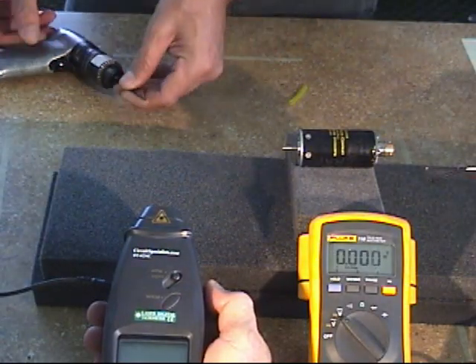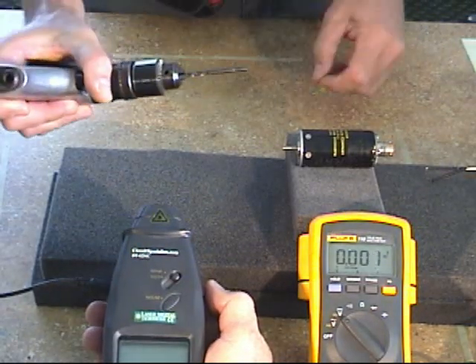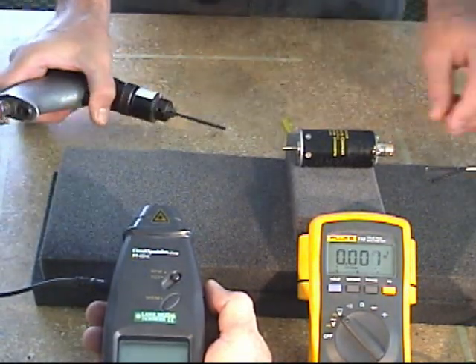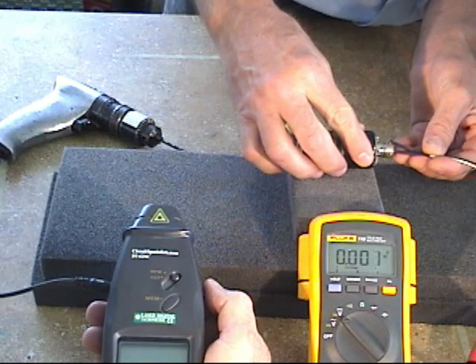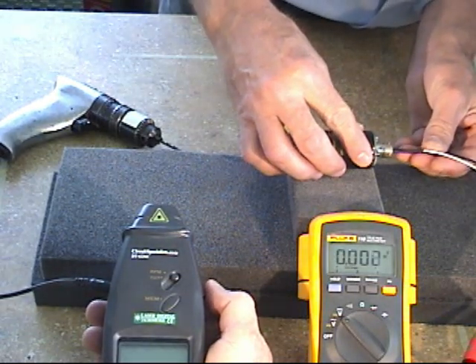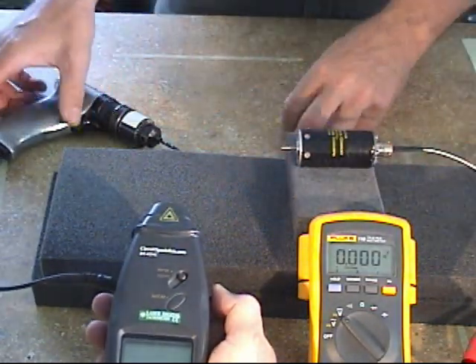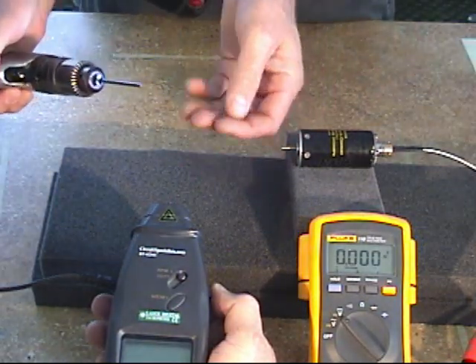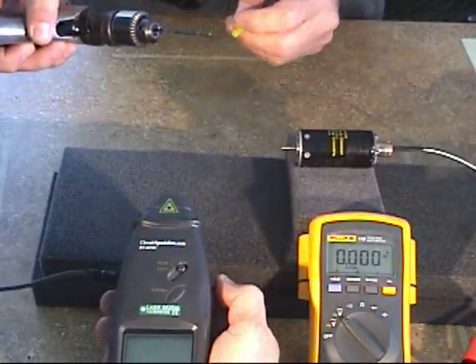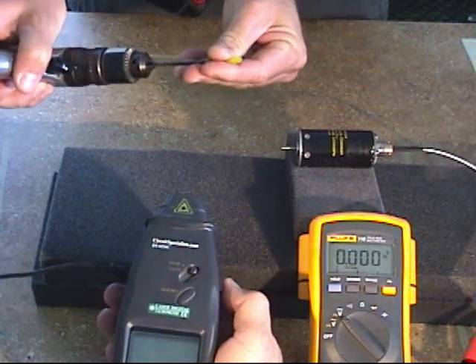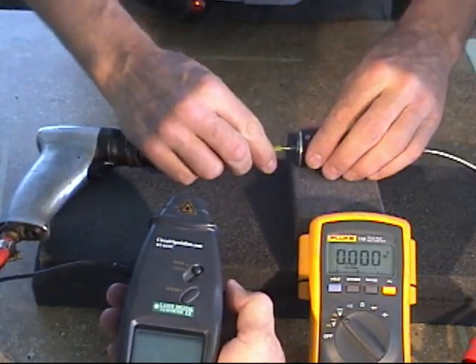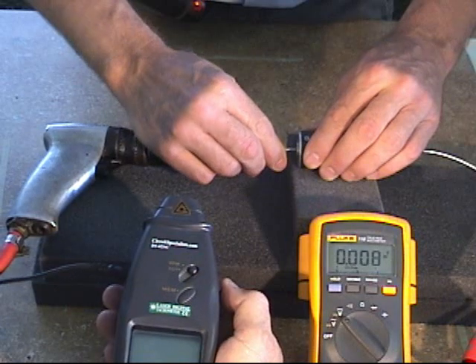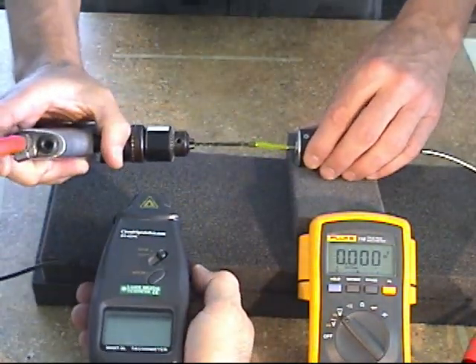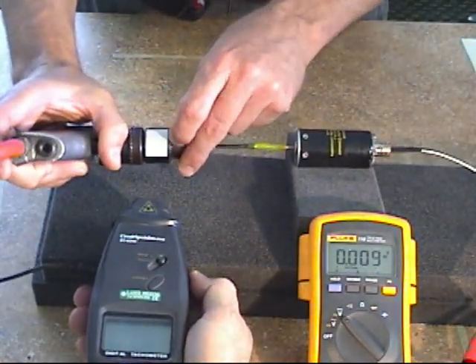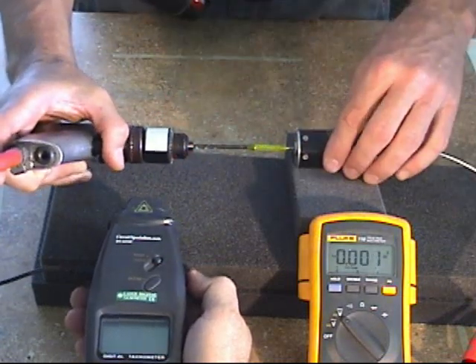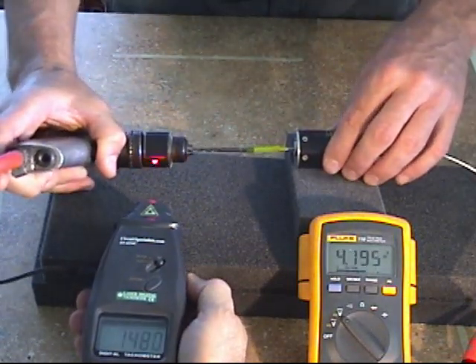This time we'll use an air drill and a little regulator to drive the motor generator to a fixed RPM to test the voltage. Sample pin A and pin C on the back here. Voltmeter set to volts. We're expecting about 5 volts or so. Piece of flexible weed eater line and a number 30 drill installed backwards in the drill is good enough for an expedient tach driver. And to get our little tachometer to hit, we had to have a little bit of black tape and a little bit of reflective tape there. That'll cause the tachometer to hit a little bit better.